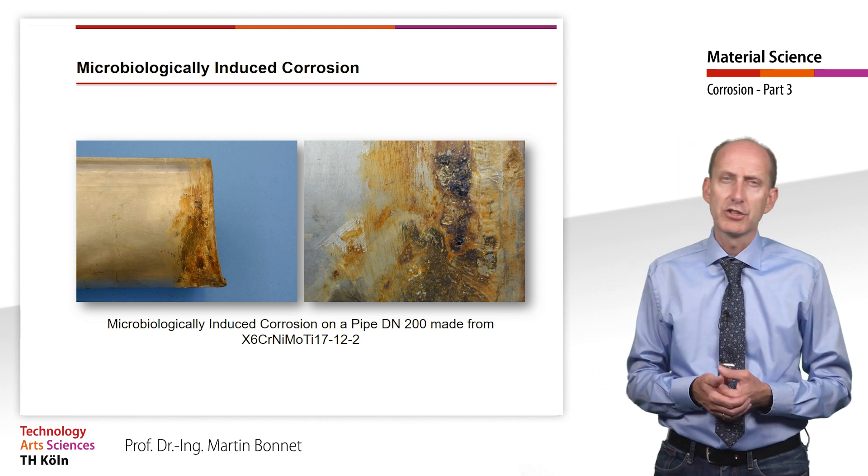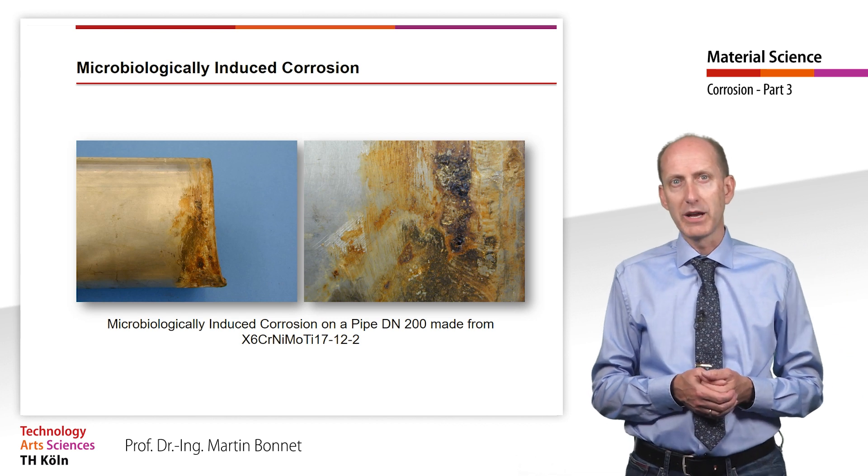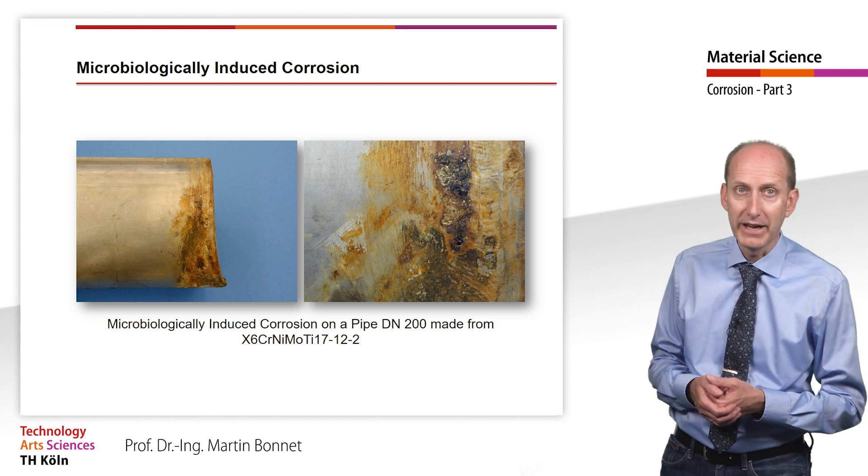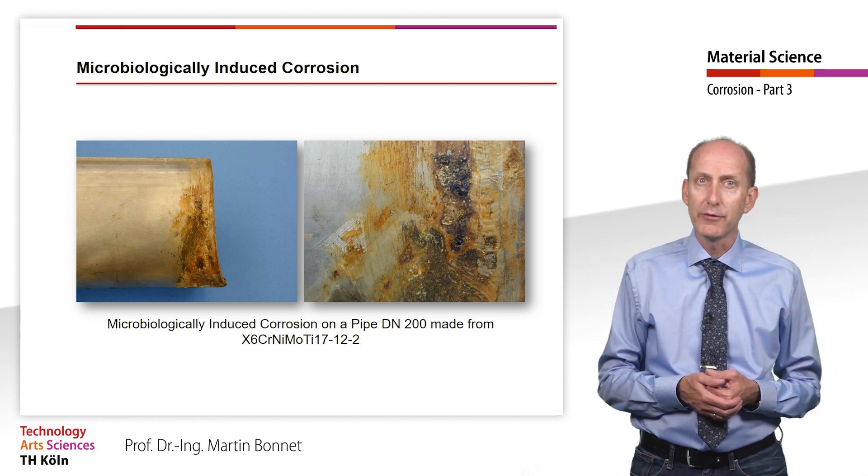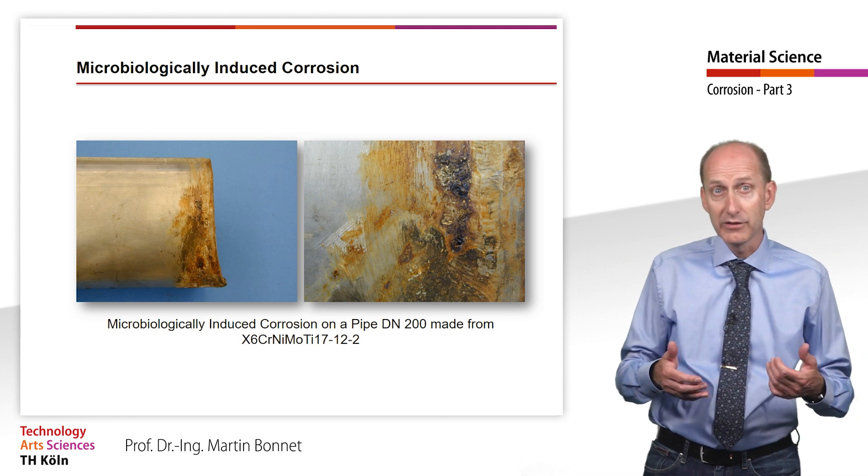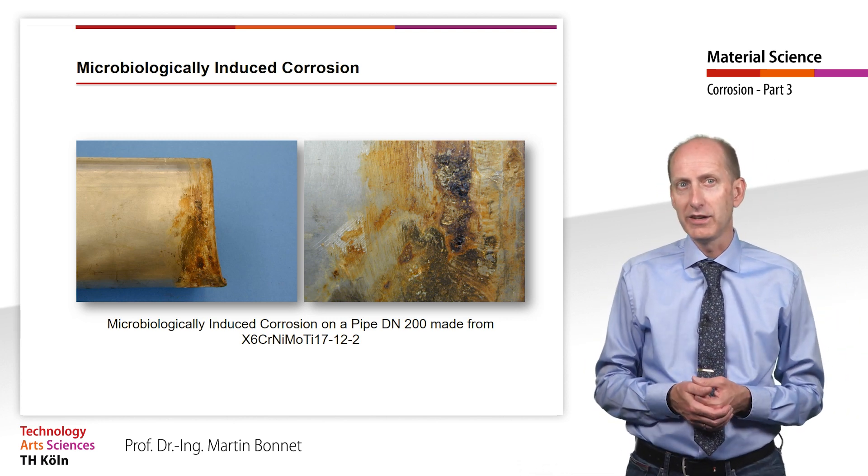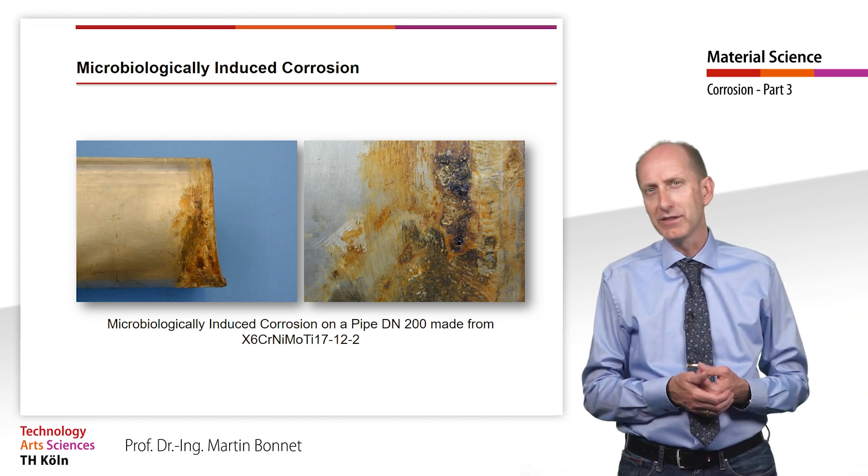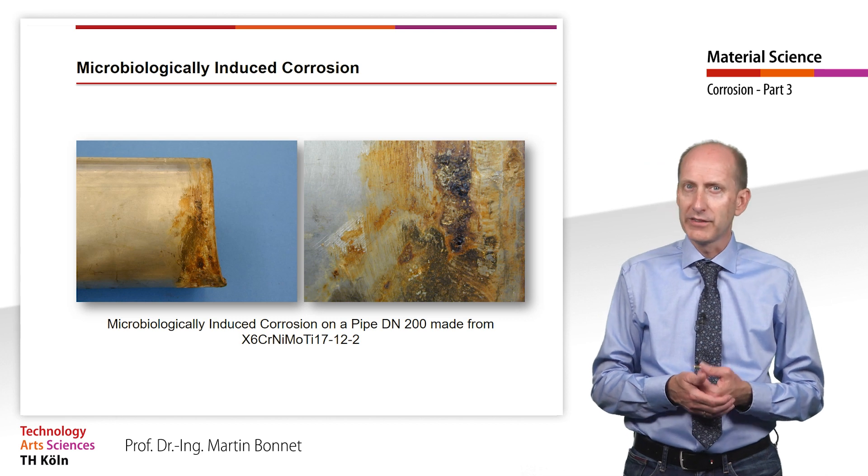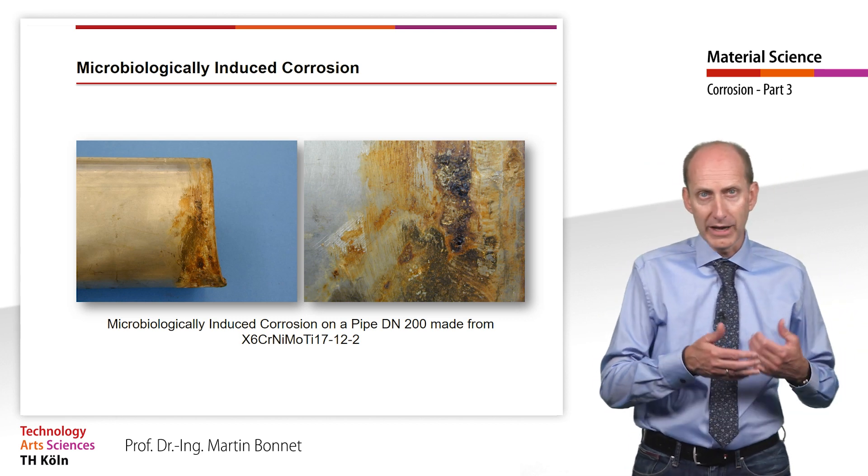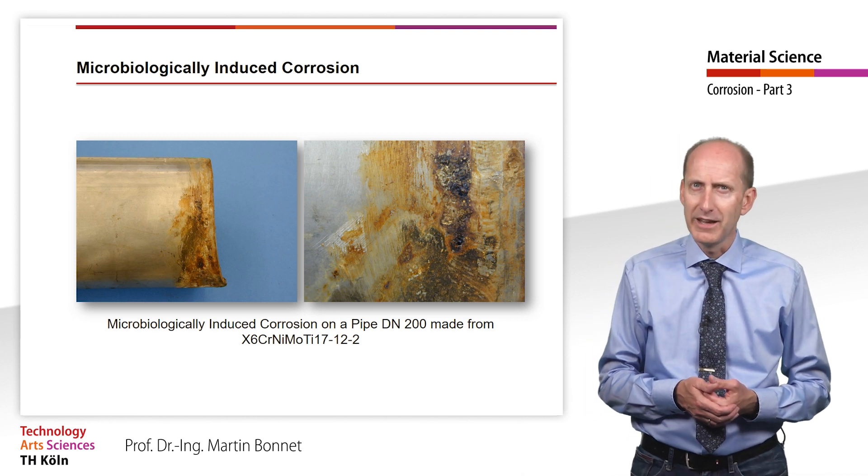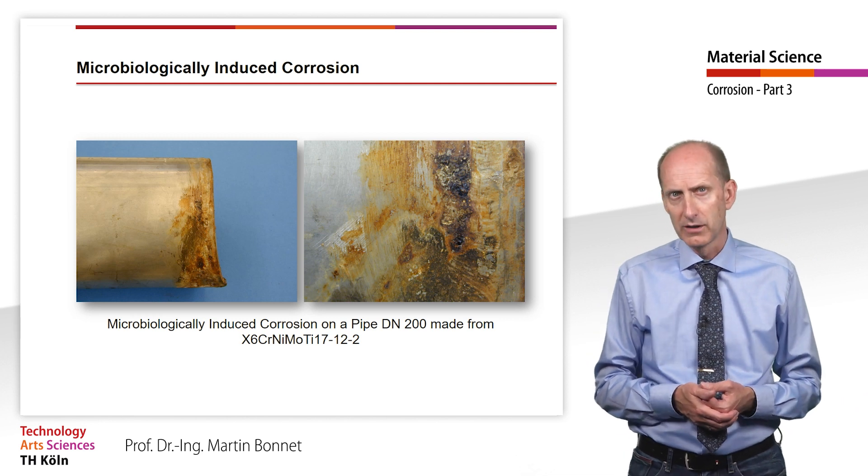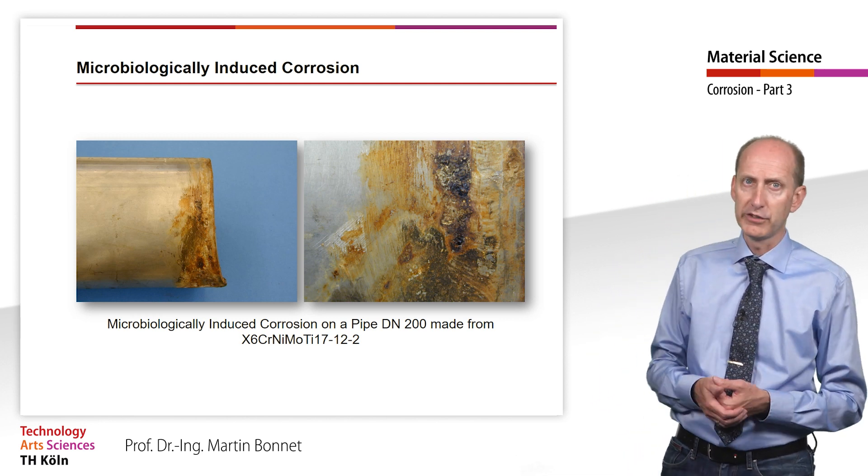These photos show a severe case of damage caused by microbiologically induced corrosion. In a wastewater treatment plant, the damage shown occurred after only half a year of use, despite the use of high-quality, high-alloy stainless steel. They used an X6CrNiMoTi17-12-2, that is a stainless steel with sufficient chromium, with enough molybdenum to prevent pitting corrosion, and with additional titanium to stabilize the steel against intergranular corrosion. So how could this severe damage have occurred?